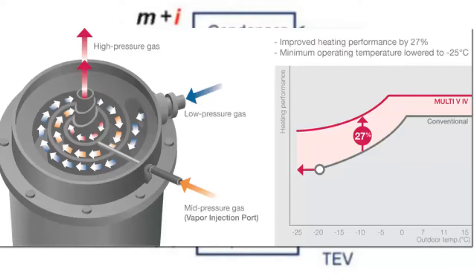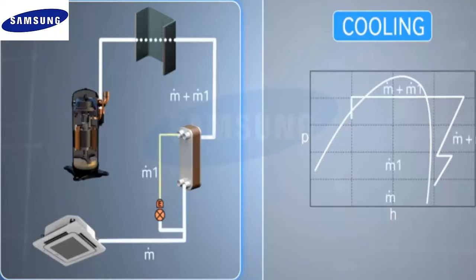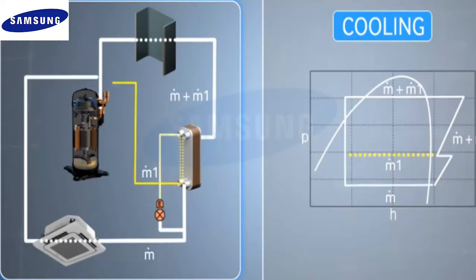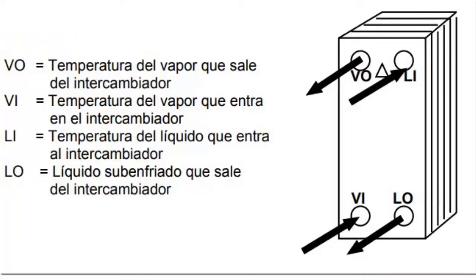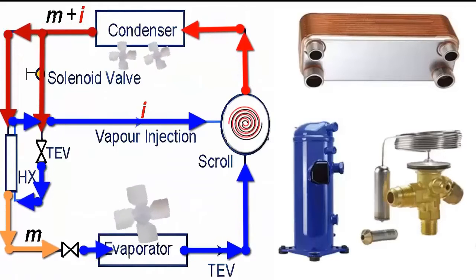This cycle offers numerous advantages, including greater cooling capacity and a better coefficient of performance (COP) compared to conventional cycles. Vapor injection technology is particularly effective at low evaporation temperatures, where greater capacity and efficiency are required.